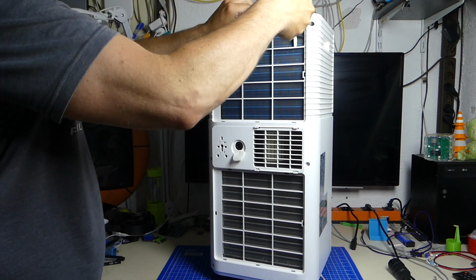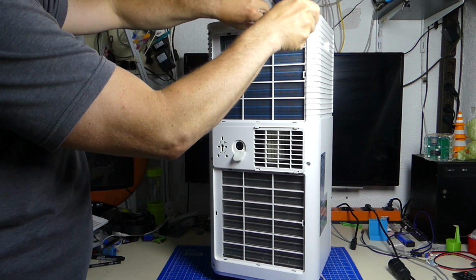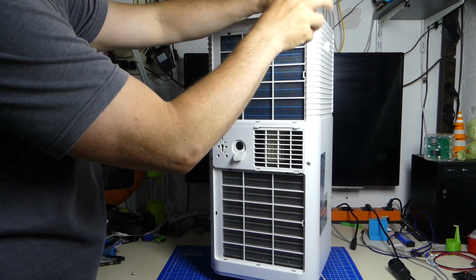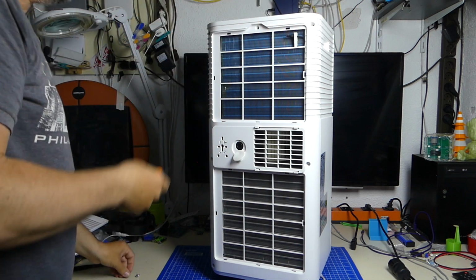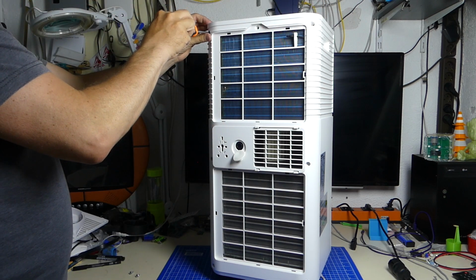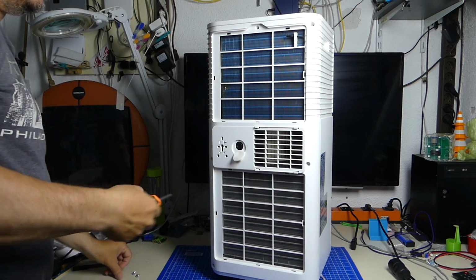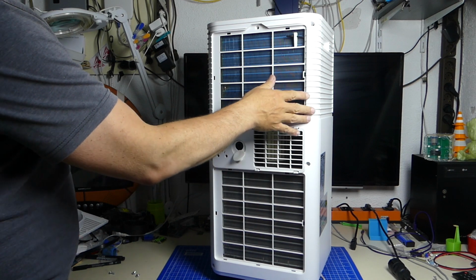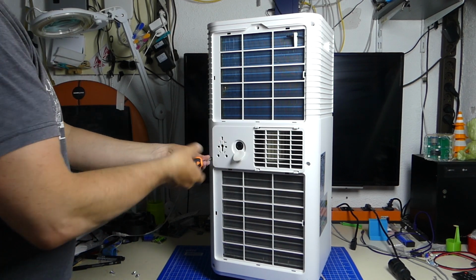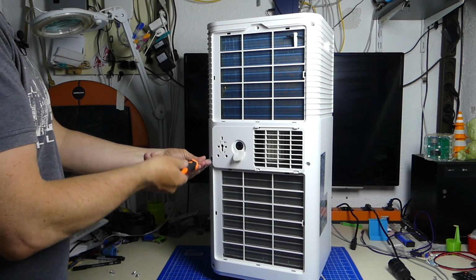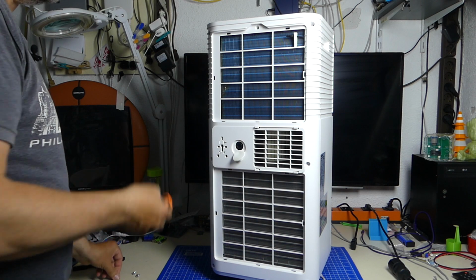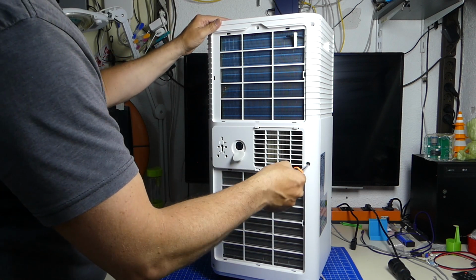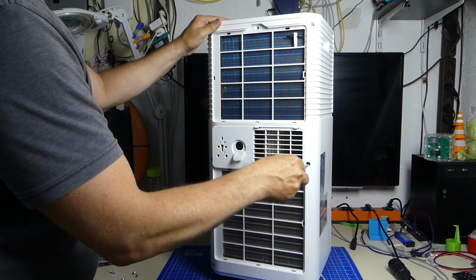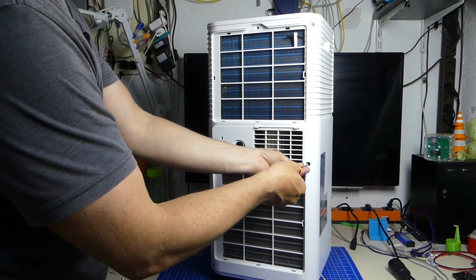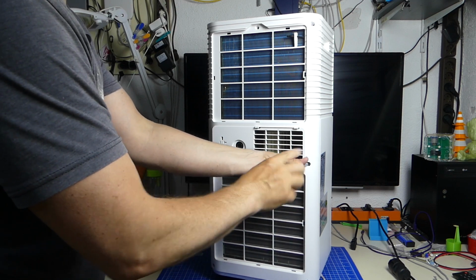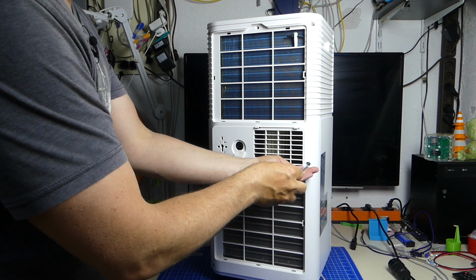This comes with one downside. We get more and more pressure in the devices all the time, which is okay, but the thing I'm worried about is that the heat exchangers become more and more closed. To get rid of so much energy in a small heat exchanger, you have to have a lot of cooling fins, and the more cooling fins you have, the easier it is to get them plugged with dust and other debris. You have to make sure you keep these things absolutely pristine clean.